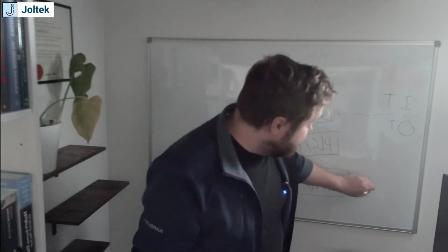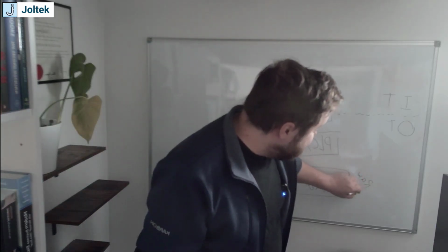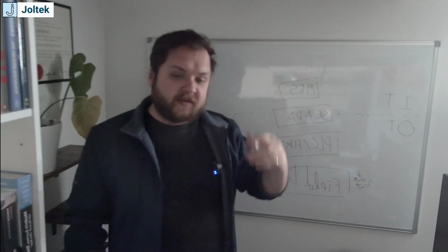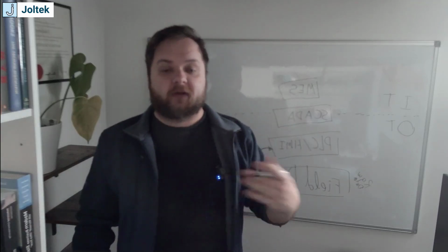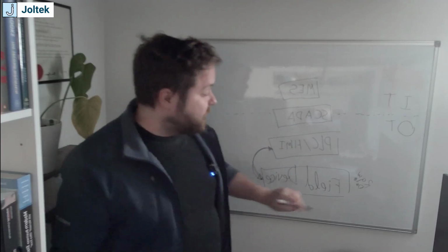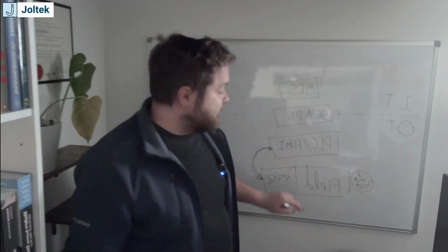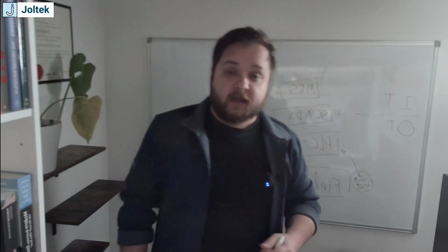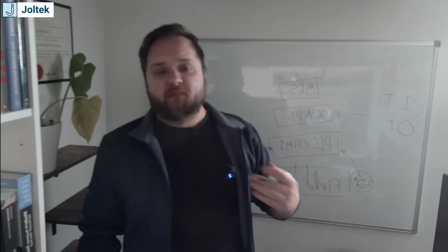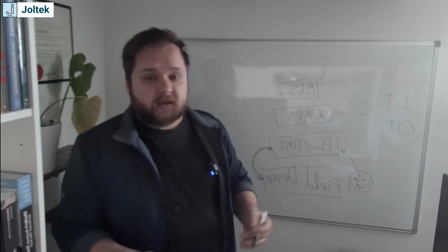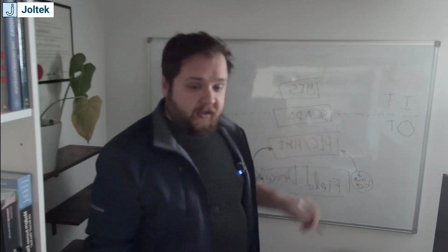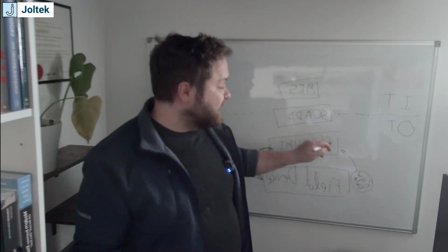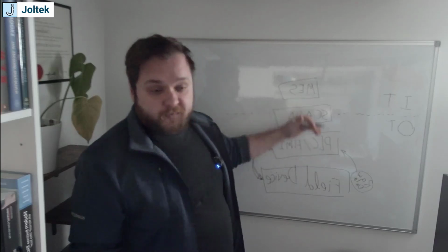So this data is not going to be raw, and this is something I didn't necessarily discuss this time, but here I'm going to put a raw data label, which is coming from your field devices. Your sensor is going to update every single time, continuously reading the level of your tanks, the temperature of your tank, etc. This raw data is then sent to the PLCs. PLCs are going to capture raw data, and they rarely forward it before transforming it in some way. It can be done, but usually that's done at the SCADA or maybe historian or edge device layer. Ultimately, this raw data lives in the PLC and HMI before it's sent anywhere else.